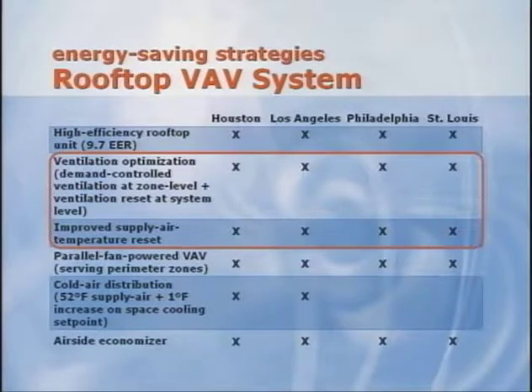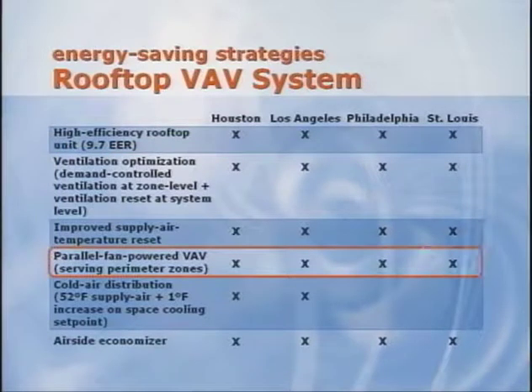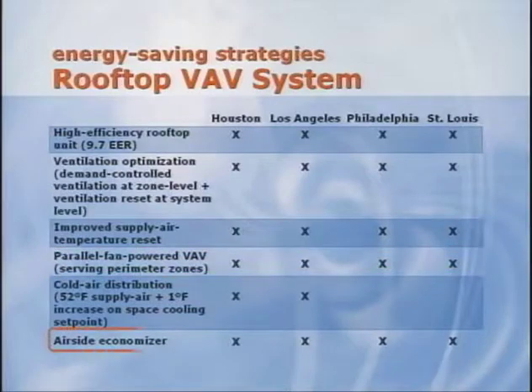John will explain these in a minute. Parallel fan-powered VAV terminals were used in the perimeter zones, and the rooftop units included airside economizers. More savings could likely be achieved in St. Louis with the use of additional energy-saving strategies. For example, cold air distribution could also save energy, but for our example, this strategy was not needed in St. Louis to reach the minimum 14% threshold.